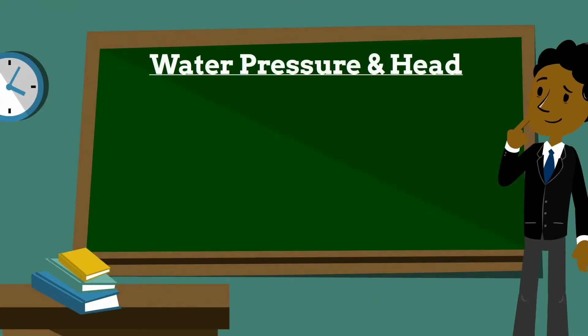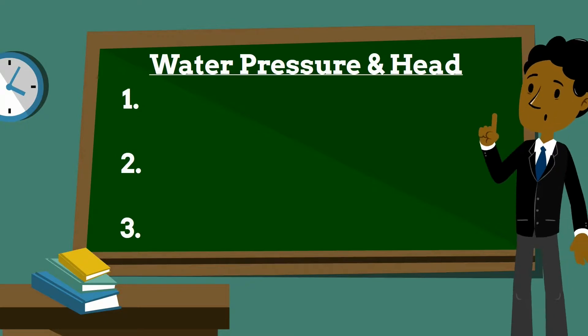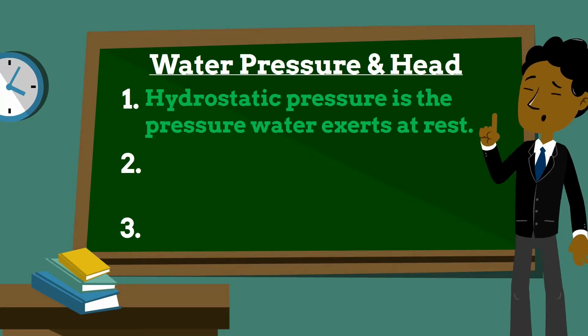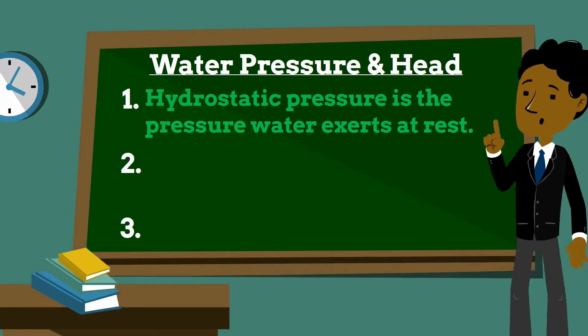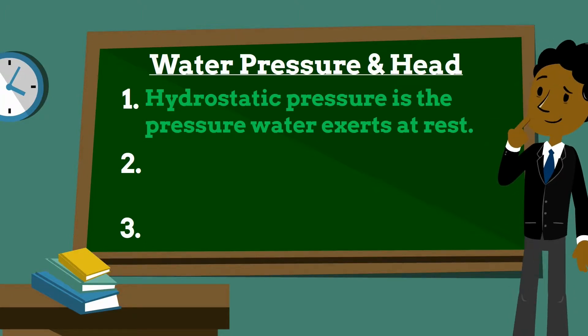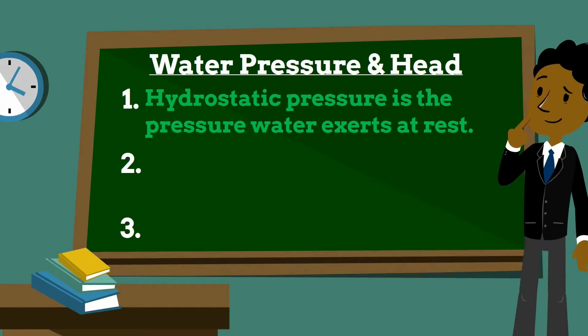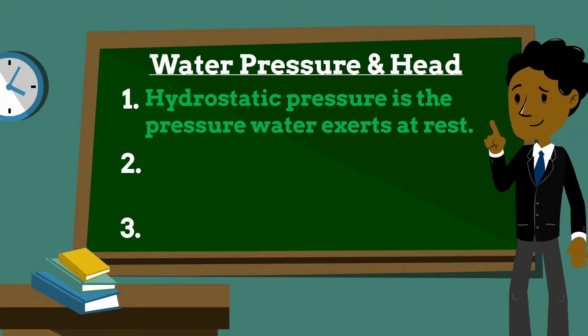Today we will talk about water pressure and head. The pressure that water at rest exerts is called hydrostatic pressure. The following important principles always apply: pressure depends only on the height of water above the point in question; pressure increases in direct proportion to the depth; pressure in a continuous volume of water is the same at all points at the same depth; and pressure at any point in the water acts in all directions at the same magnitude.